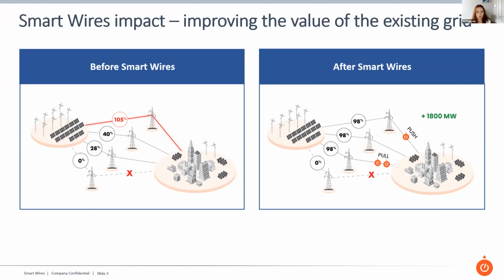So what power flow control tries to do is to get access to that spare capacity on the underutilized lines by controlling the impedance of the different lines in the meshed grid. So when you look at what's happening with the Smart Wires equipment, we can do both increases and decreases of impedance. So if we increase the impedance of the line that's overloaded, we can push power off it, and it'll naturally flow onto the other parallel lines. And we can encourage that even more by decreasing the impedance of those circuits by operating in a capacitive mode, or a pull mode, as we often call it.